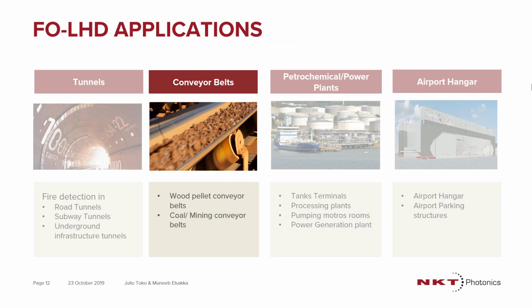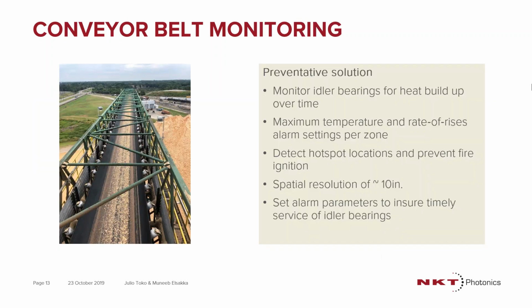Next application, conveyor belts, is another prominent application for fiber optic linear heat detection, where you take more of a proactive approach to heat detection. So in conveyor belt monitoring, really the point of interest are the idler bearings heating due to friction. And really what you want to do here is take a preventative approach in the design of the system. Not so much detecting the fire, but you can use this fiber optic system to detect a rate of rise or set a pre-alarm parameter for an unwanted heat signature of an idler bearing. This allows you to service it properly.